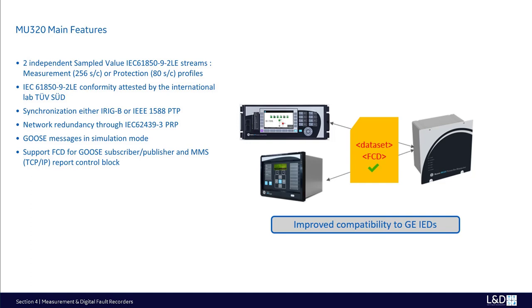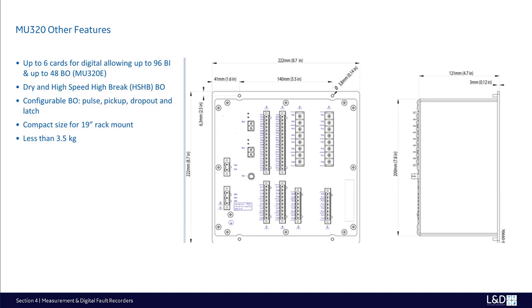MU320 supports functionally constrained data FCD for Goose, subscriber, publisher, and MMS TCP/IP report control block. Other features are up to 6 cards for digital inputs, allowing up to 96 BI and up to 48 BOs as remote I/O devices. For MU320E, they are high-speed, high-break output contacts with the operating time being less than 0.2 millisecond. The binary outputs are configurable to be pulse, pickup, dropout, and latch. The MU320 is a compact size to fit 19-inch rack mount installation, suitable to be placed in cabinets and kiosks in the yard. The weight of MU320 is less than 3.5 kg.